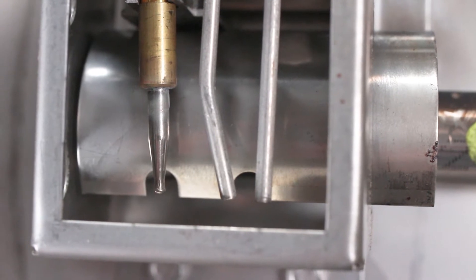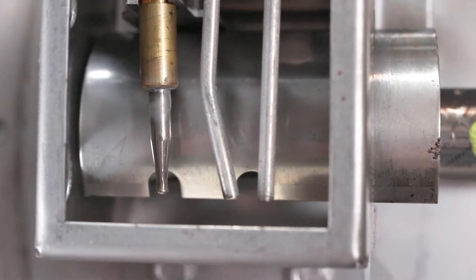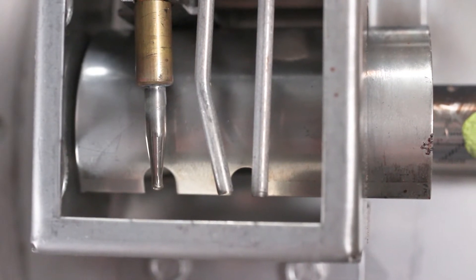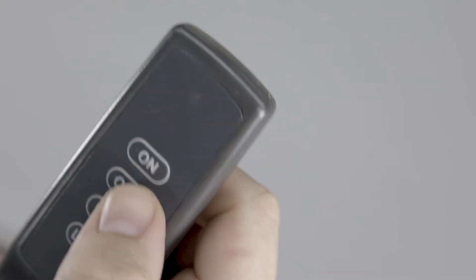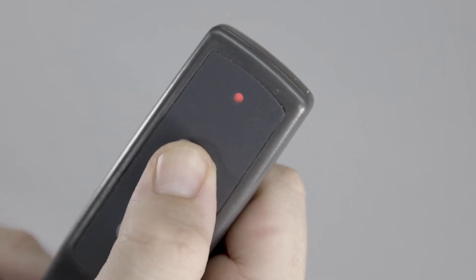This error is the ignition safety error. It means that the burner or pilot light did not successfully light within 15 seconds. To clear the fault, press the off button on the remote transmitter, then press and hold the on button for three to six seconds to attempt re-ignition.